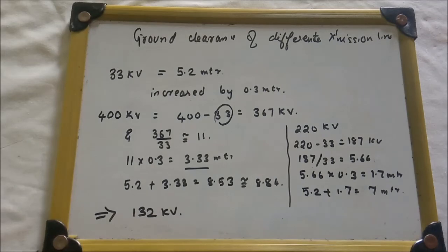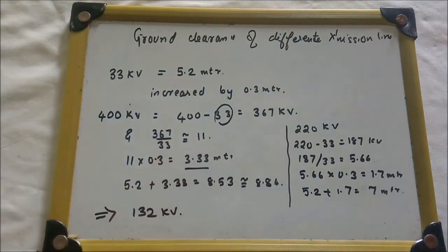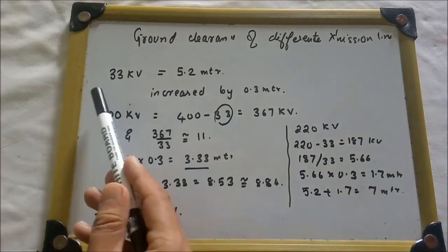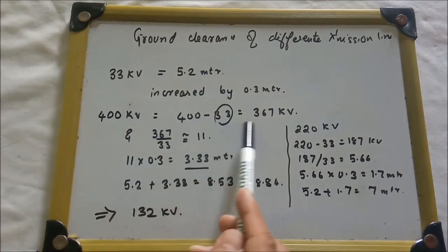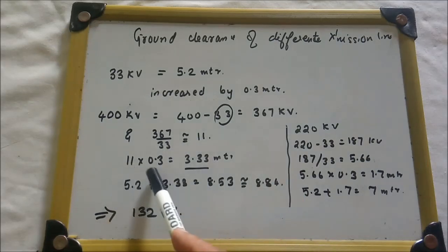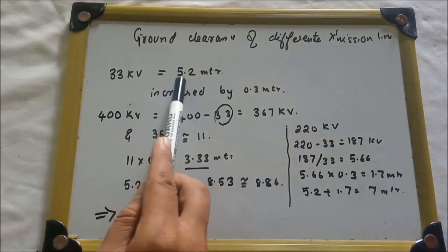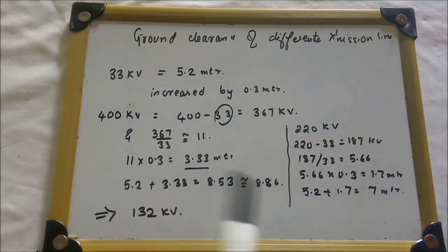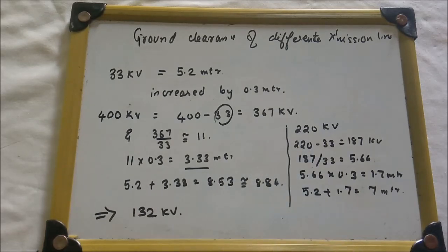So we know how to solve: the minimum ground clearance for 33 kV is 5.2 meters, and above 33 kV we increase by 0.3 meters. For 400 kV: 400 minus 33 equals 367, divided by 33 gives 11, multiplied by 0.3 gives 3.33 meters, added to 5.2 gives 8.84 meters. The same method applies for 220 kV and 132 kV.